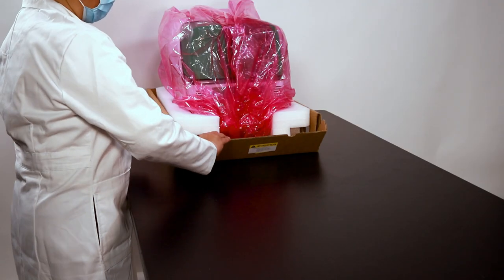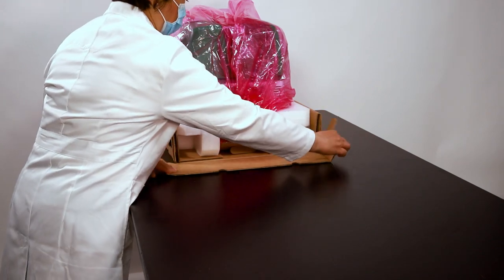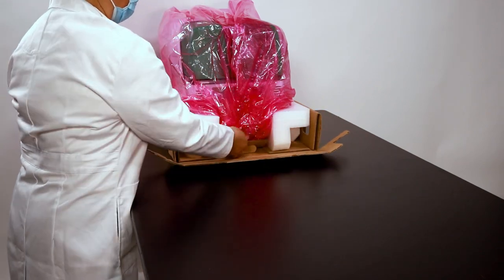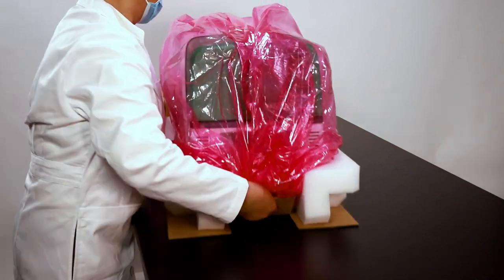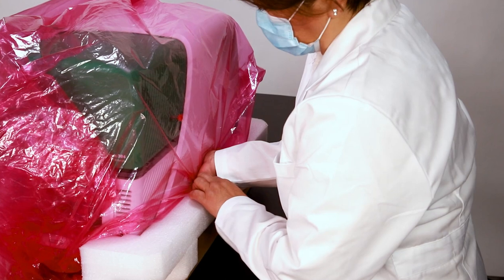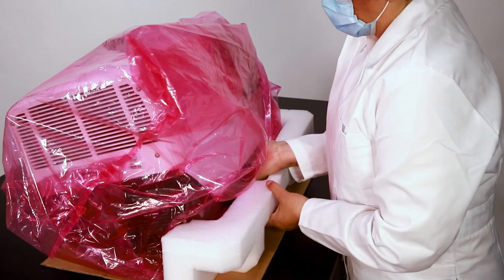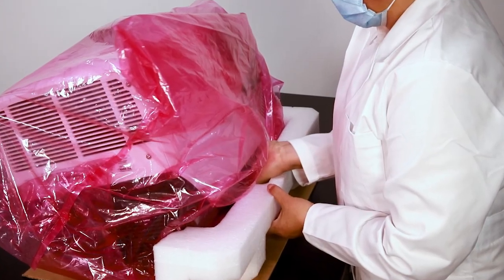Pull down the flap located at the cardboard base. Using the handle on the inner cardboard tray, slide the inner tray with the instrument onto the bench top. There are two lift points on either side of the instrument that can be used to lift or move the instrument.